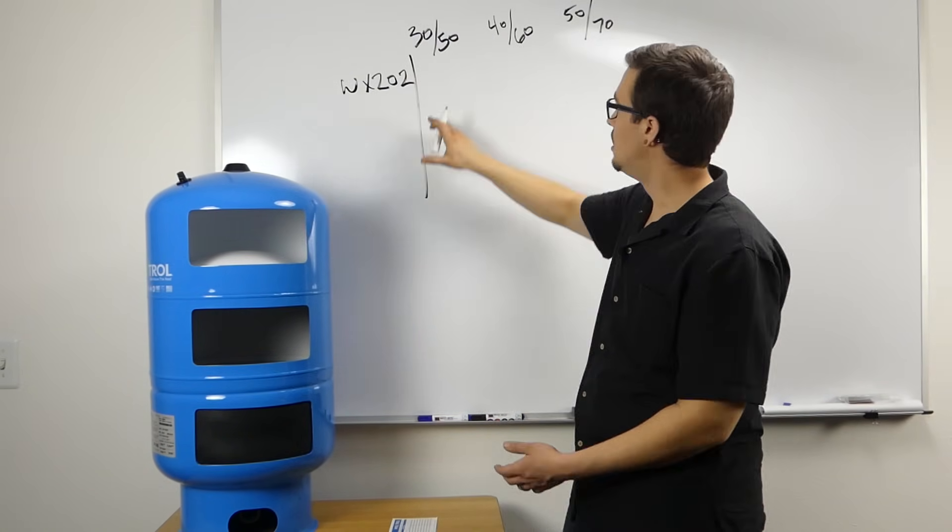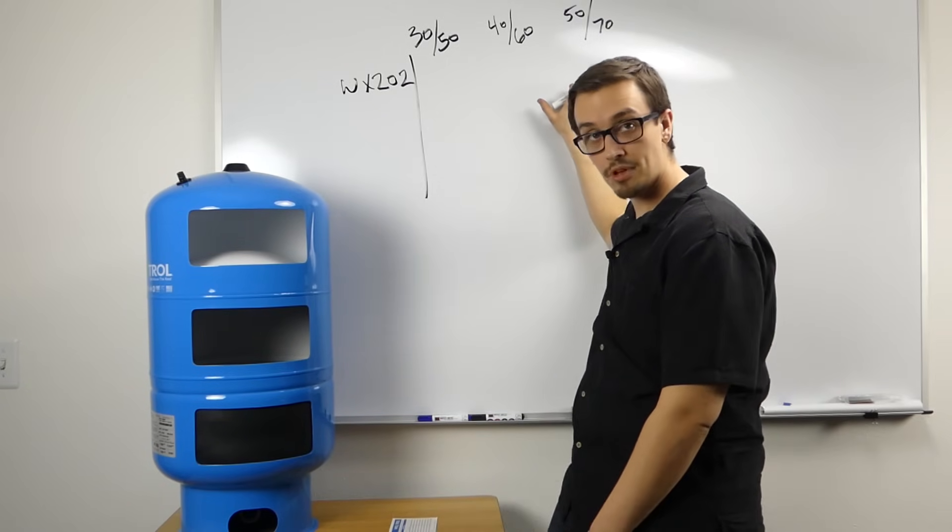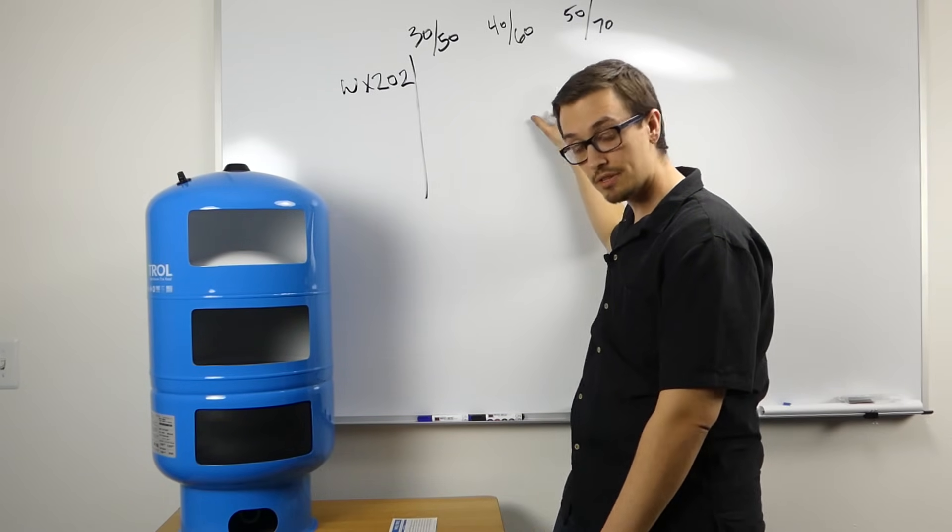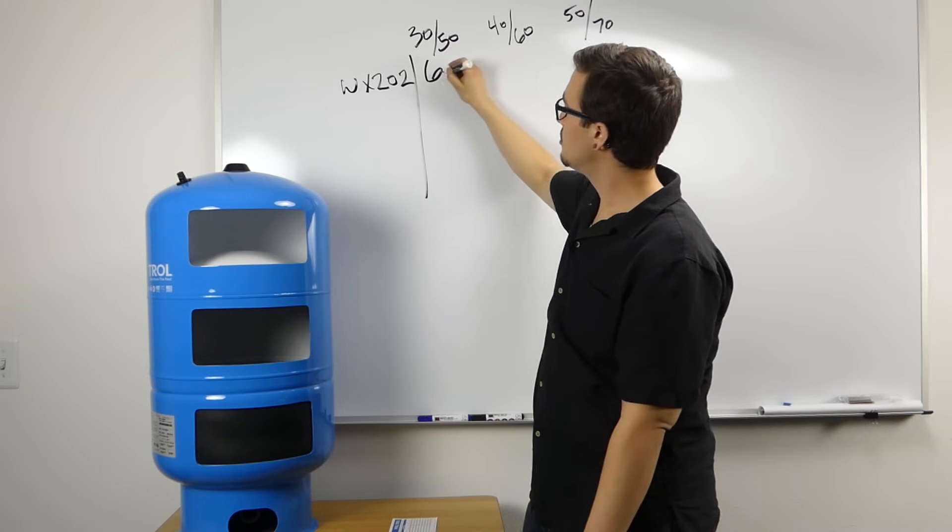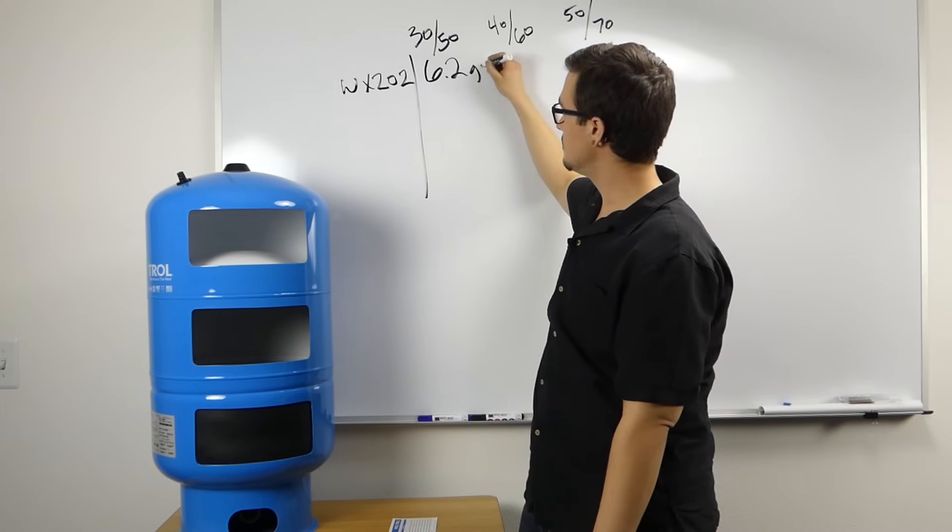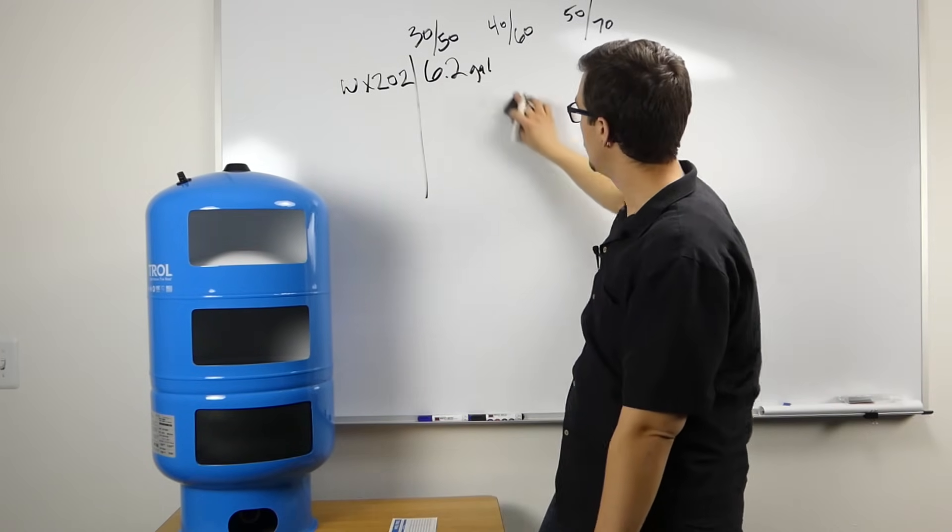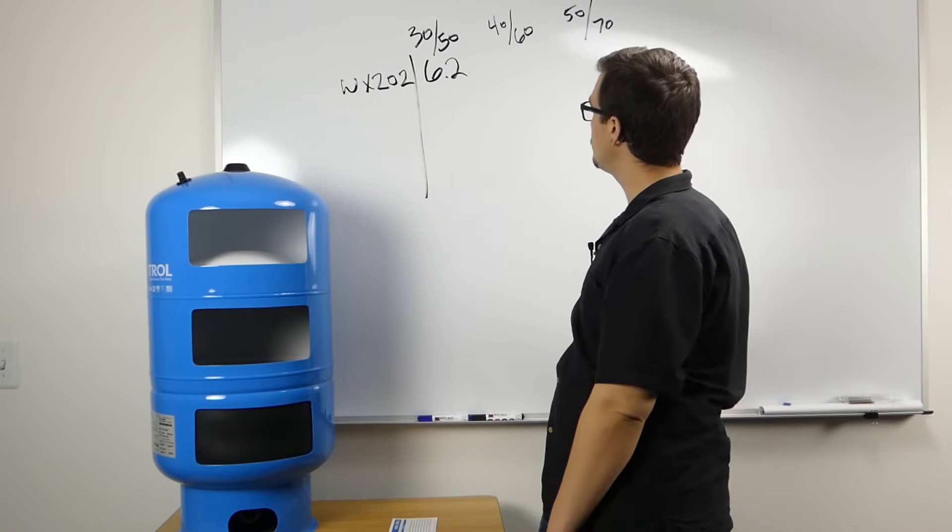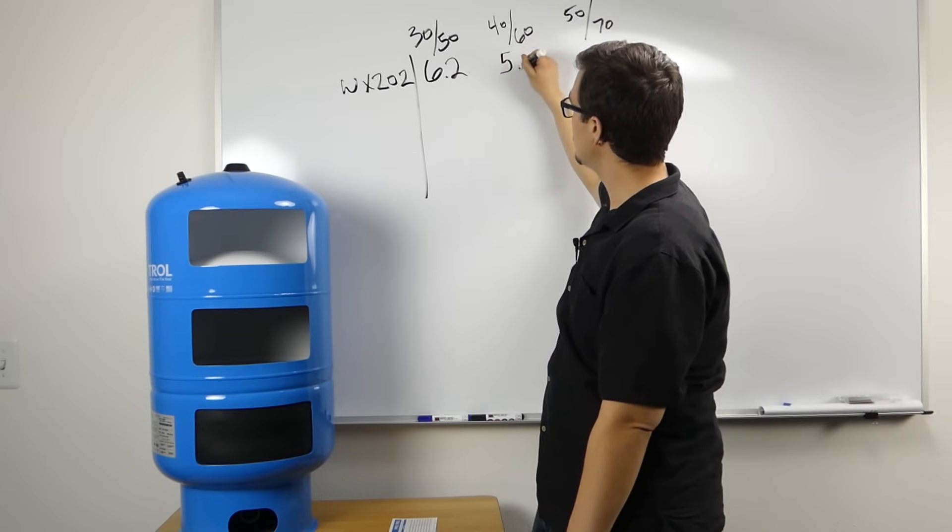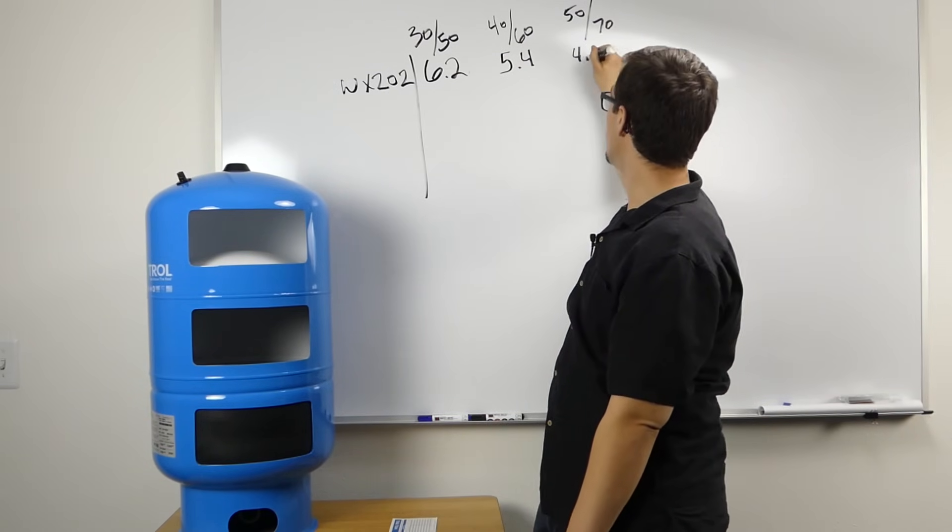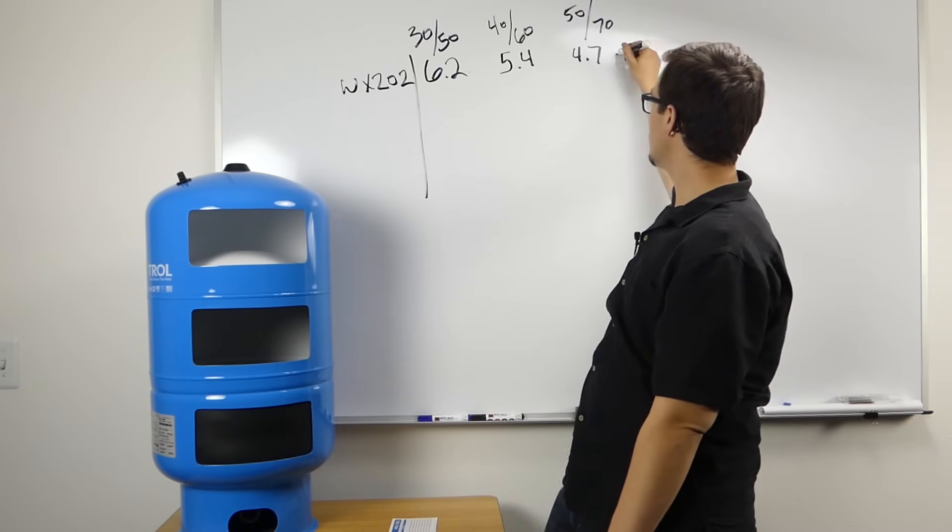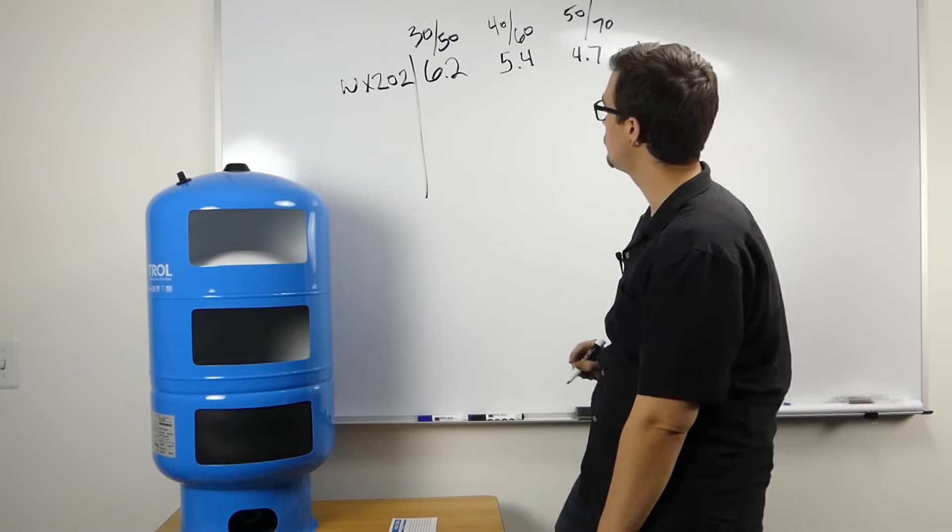We've got a few different drawdown capacities that actually apply to this pump. At 30/50, you've got 6.2 gallons. At 40/60, it's 5.4, and then 4.7 at 50/70. This is gallons of drawdown.